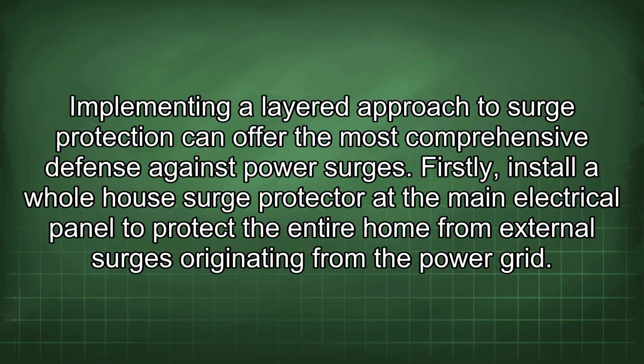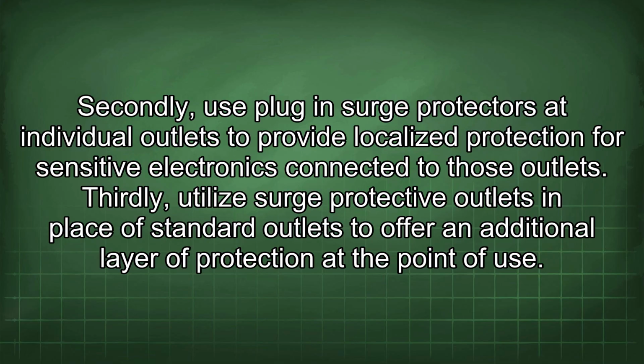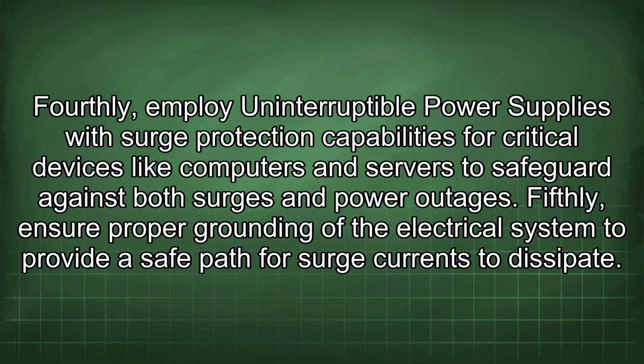Firstly, install a whole house surge protector at the main electrical panel to protect the entire home from external surges originating from the power grid. Secondly, use plug-in surge protectors at individual outlets to provide localized protection for sensitive electronics connected to those outlets. Thirdly, utilize surge protective outlets in place of standard outlets to offer an additional layer of protection at the point of use. Fourthly, employ uninterruptible power supplies with surge protection capabilities for critical devices like computers and servers to safeguard against both surges and power outages.